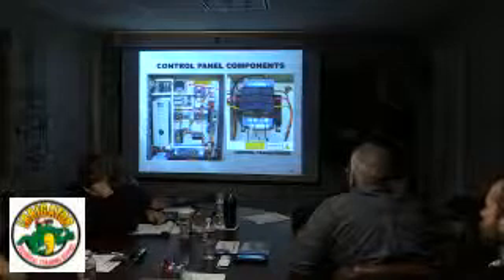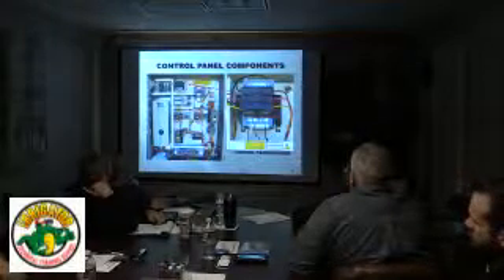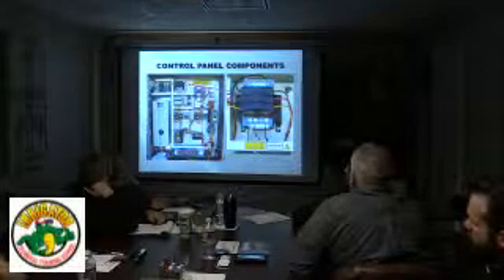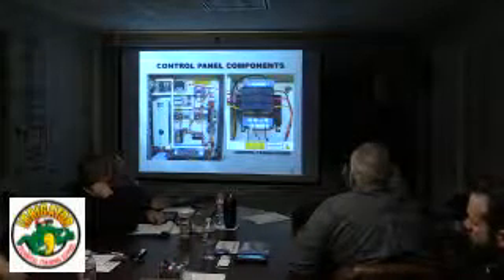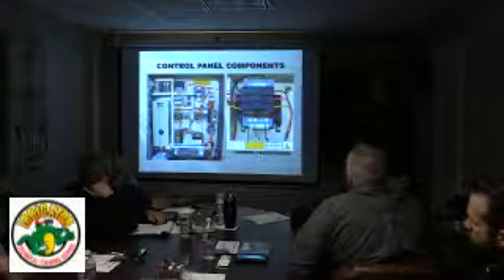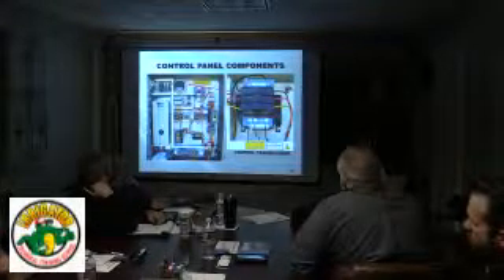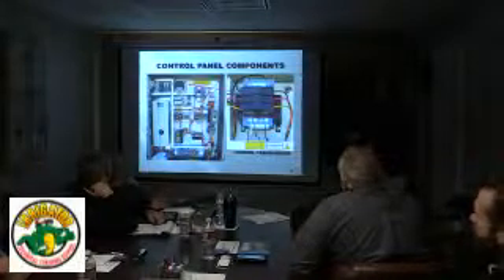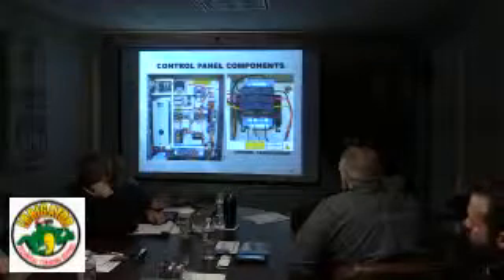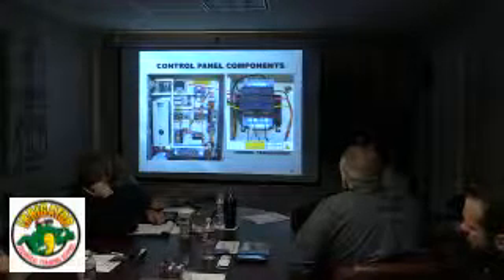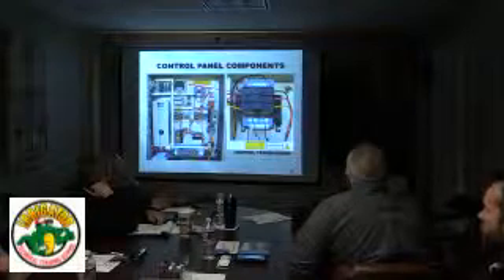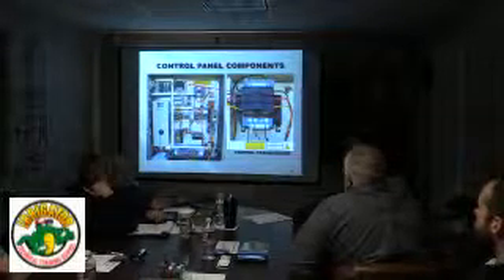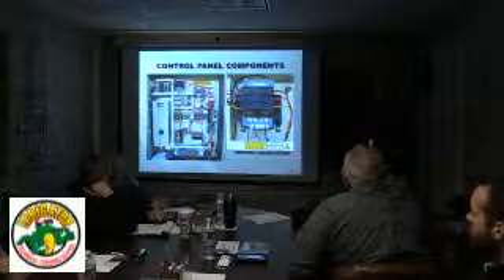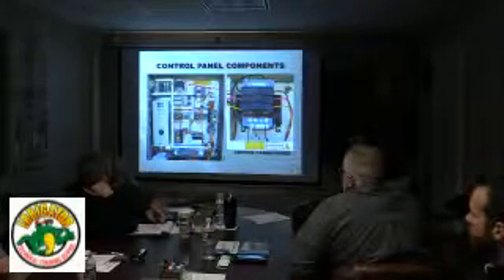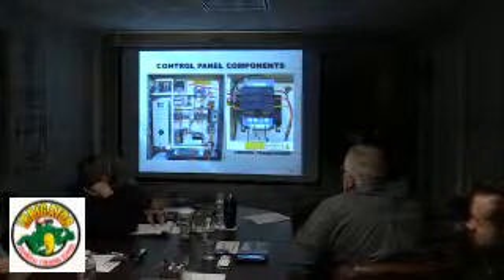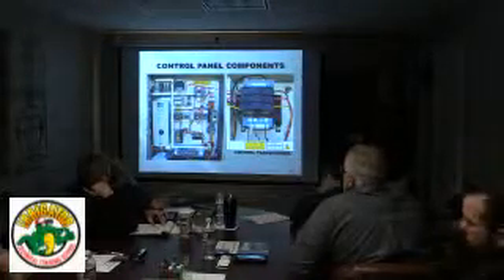This will jump down to the top of this very last breaker, and then from that breaker it's going to jump down to the purple wire that's here, and then this is going to wire out to that solenoid valve on the system. So again, as soon as the main drive starts, it actually runs from here up to the PLC and then down to here. And then when the PLC turns the main pump on, the relay output of the PLC closes and energizes that 24 volt AC coil on there. Does it run off one of the slims up there? No, I think this one actually does have a purple wire right there. Straight PLC, out? Okay, so it comes straight off of that.